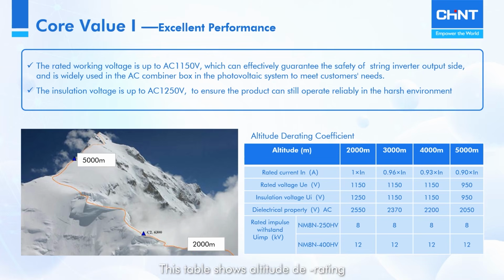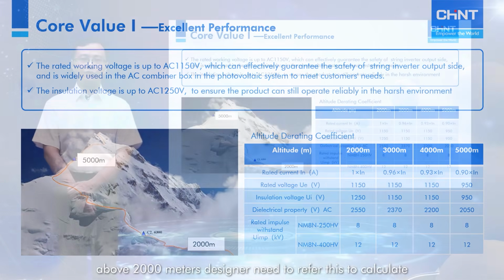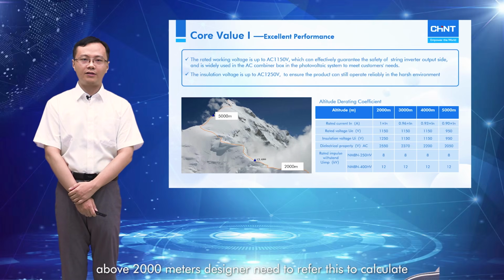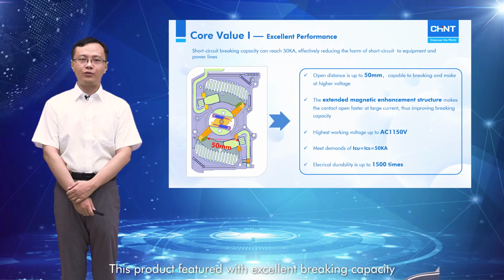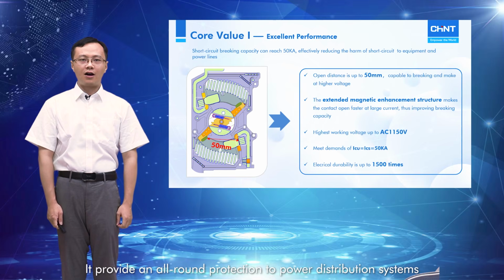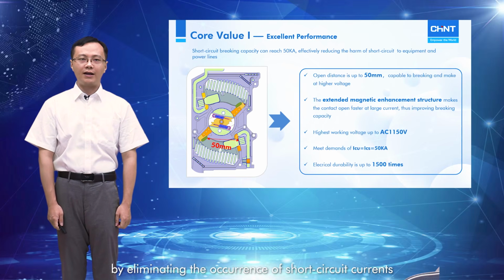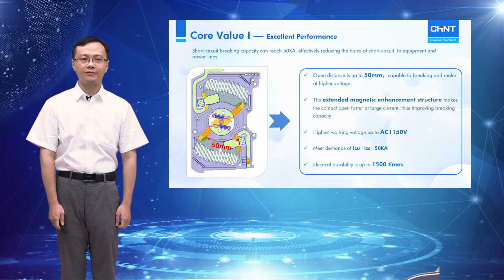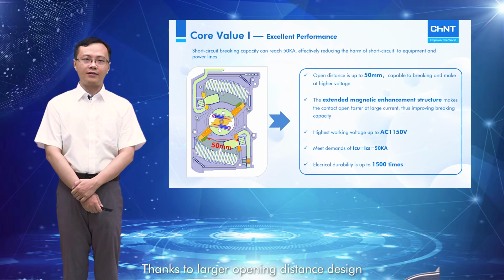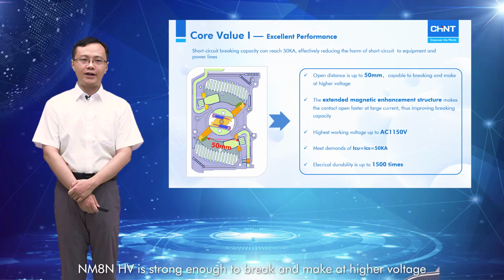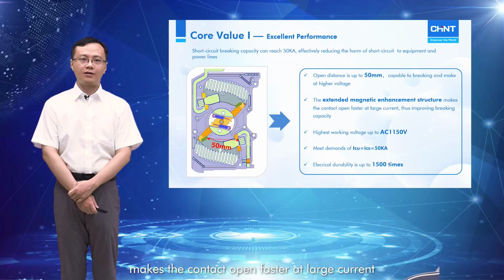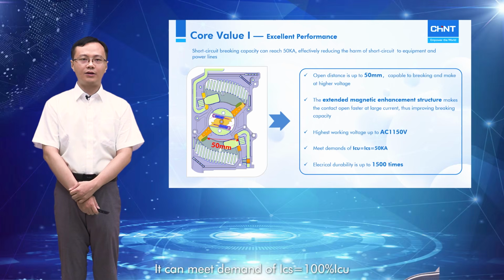environment. This table shows the altitude derating factor. When the product is installed at high altitude above 2000 meters, designers need to refer to this table to do the calculations. This product features excellent breaking capacity. It can provide all-round protection to the power distribution system by eliminating the occurrence of short-circuit current. Thanks to the large opening distance design, NM8N is strong enough to break and make at higher voltage. The extended magnetic enhancement structure makes the contact open faster at a larger current. Thus, it improves the breaking capacity, so it can fully meet the demands of ICS equal to 100% ICU.